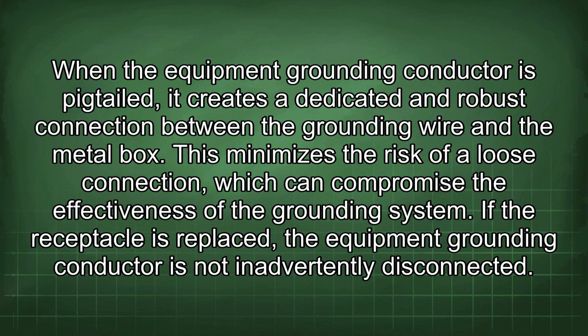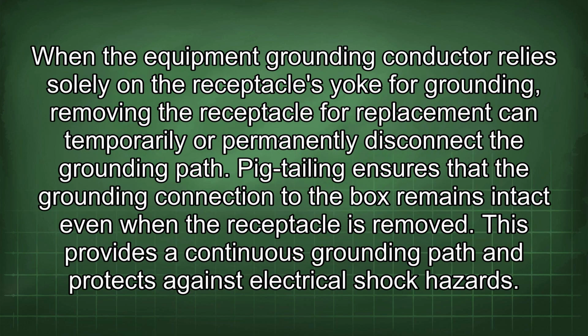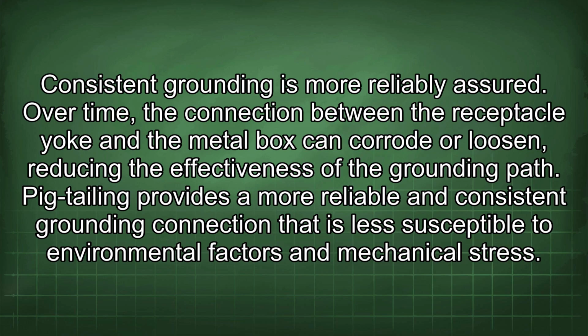If the receptacle is replaced, the equipment grounding conductor is not inadvertently disconnected. When the equipment grounding conductor relies solely on the receptacle's yoke for grounding, removing the receptacle for replacement can temporarily or permanently disconnect the grounding path. Pigtailing ensures that the grounding connection to the box remains intact even when the receptacle is removed. This provides a continuous grounding path and protects against electrical shock hazards. Consistent grounding is more reliably assured.